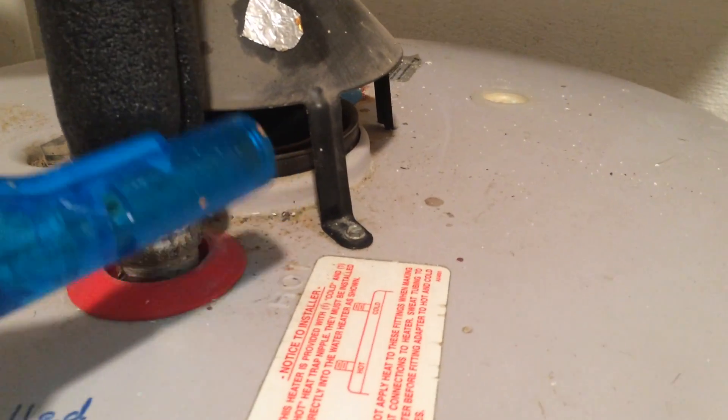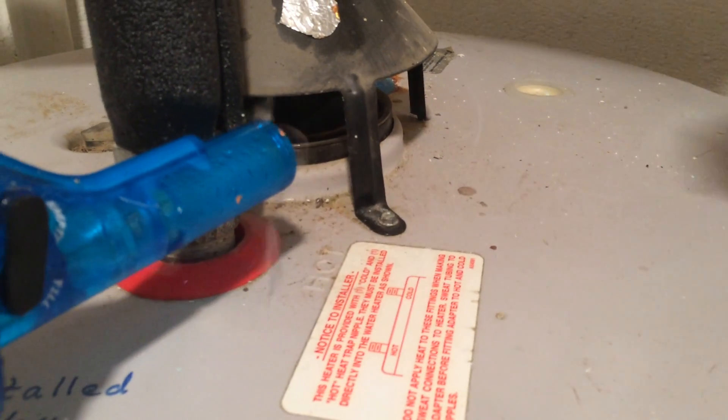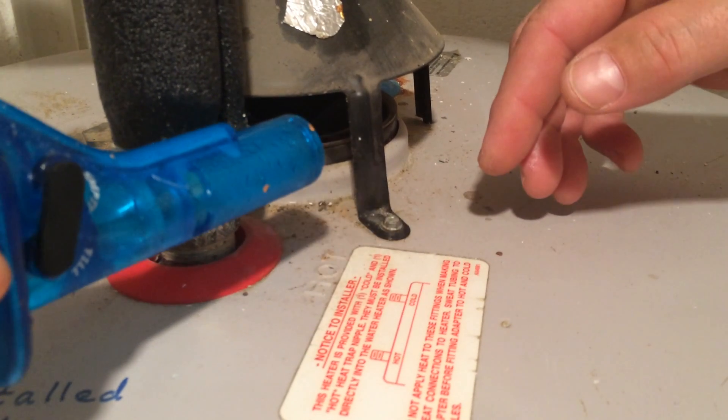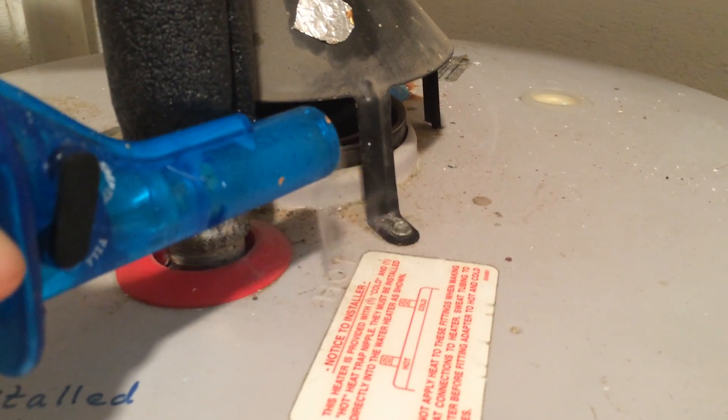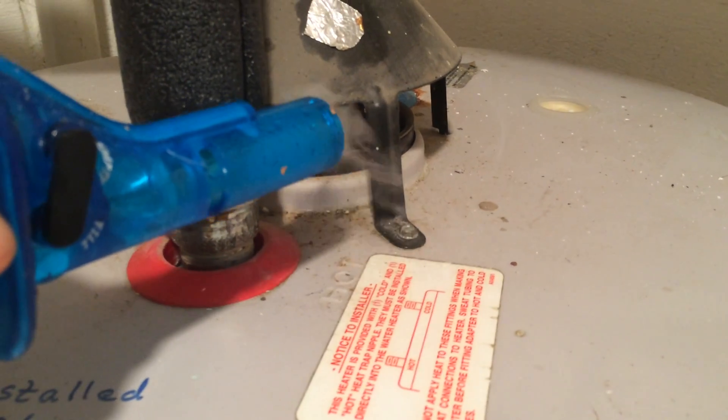It's not passing — you can feel it. Put your hand there. Now it takes a minute to start drafting, because it's got to heat the chimney up. But this is called spillage, and that's not good.